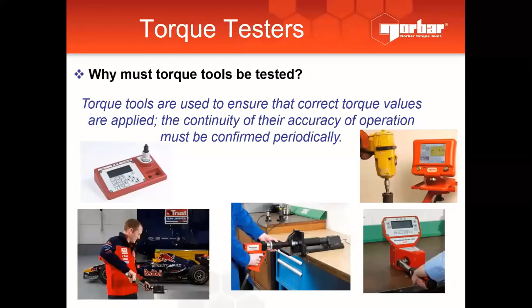Why do you need a torque tester? A torque tester is actually to ensure the correct torque value is applied. A torque tool is calibrated and valid for a year, but after 6 months you're not sure whether it's still accurate, even though it falls within the calibrated period. So you need a torque tester on-site to verify the torque tool is still within range, instead of just waiting until the calibration is due.